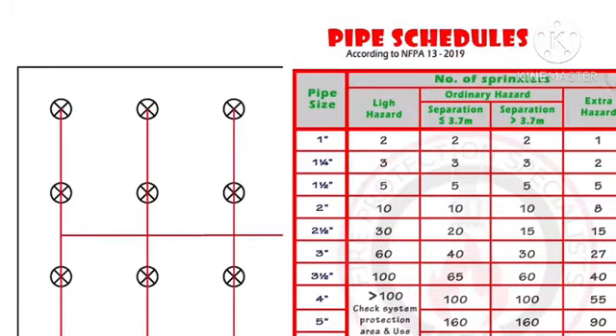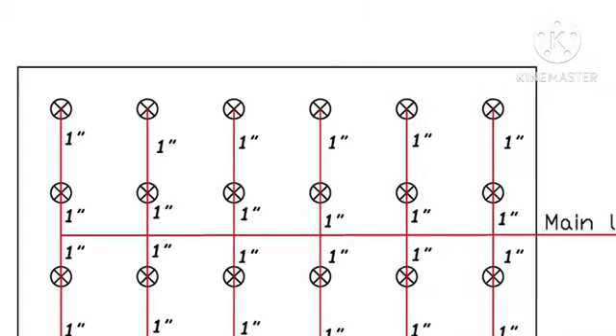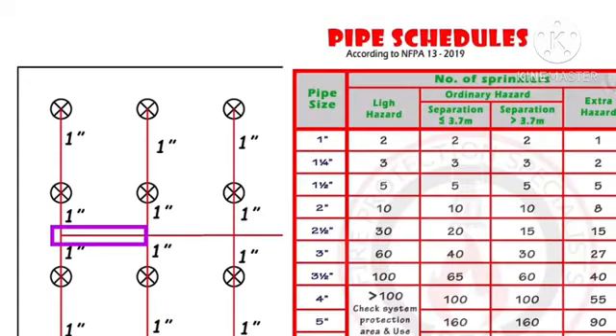Since our space is considered light hazard, and having no more than 2 sprinkler heads on each branch, the size of all branches is 1 inch. For the main line, always start from the end. This portion is feeding 4 sprinkler heads, so its size should be 1.5 inches. This portion is feeding 8 sprinkler heads, so its size should be 2 inches. And all the rest are 2.5 inches because the number of sprinkler heads is more than 10 and less than 30.